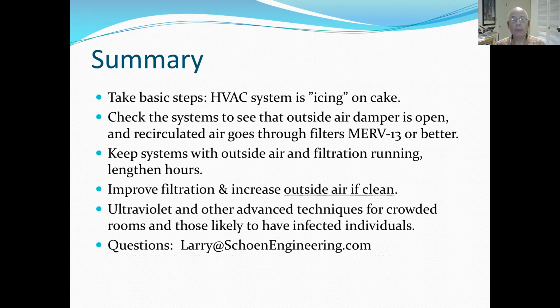Make sure your systems are running, that they're doing what you think they're doing in terms of outside air and filtration. Run them before occupancy, 1 hour, 2 hours, more if you know your system has very little outside air dilution and maybe not the best filtration, but it has some of both. If it has some of both, run it. If it doesn't have any of either, get some. Improve your filtration to the level that you can, get more outside air. Consider advanced techniques such as the ultraviolet, such as the room air cleaners that I've mentioned, if you can get a hold of them.